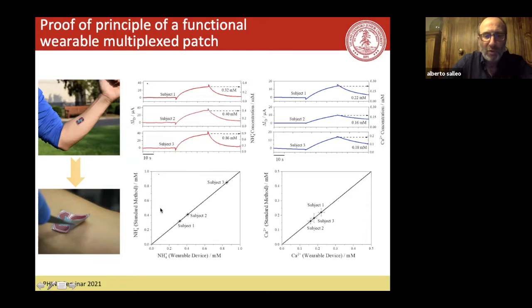And to make sure that our measurement is correct, we then measured the concentration of ammonia with a standard electrochemical electrode, and our measurement after the calibration is just about as good. And we did calcium at the same time, same thing. After we put a pulse for about 30 seconds, we measure the current at the end of the pulse, and the current is then translated into a concentration of calcium after the calibration curve is built. And then we check with our standard electrode that the concentration of calcium is what you expected based on what you get from the standard electrode.